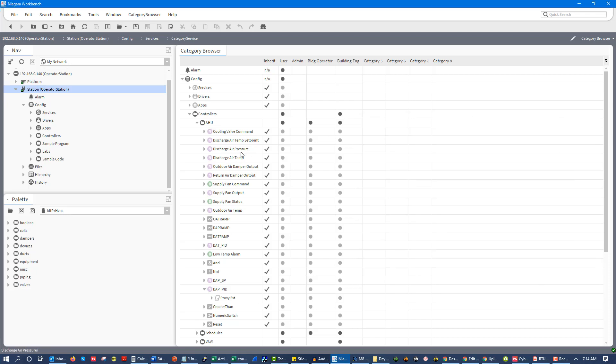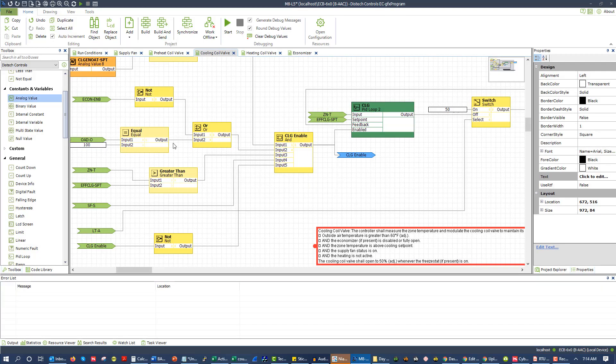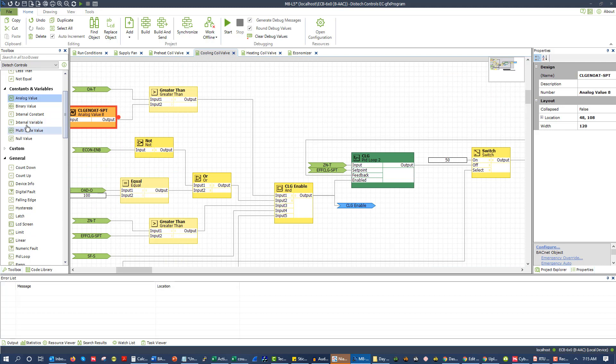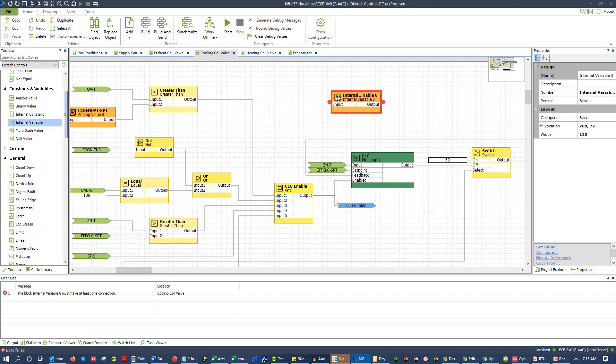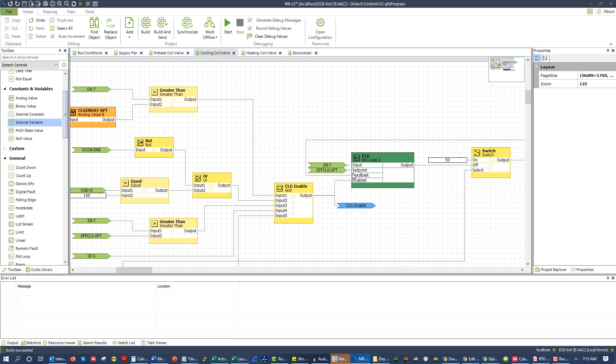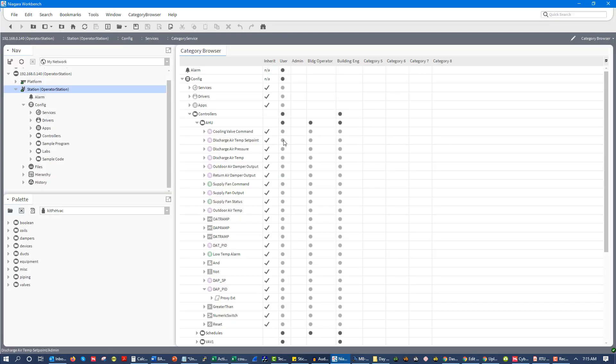Backups are especially important for a lot of us right now who, if you haven't already shut down your building and you're looking at going to shut down your building, you need to perform a backup. Because some of your points are not going to be persistent. If we open up this DISTECH software here and I add an internal variable and click on this, you'll see persists. That means when the controller resets, the value in here is going to persist. Well, there's some software where there is not persistent programming. The values are not persistent. So you really want to back them up because a lot of you are going to be turning off your buildings. You're going to go to turn back on your buildings and you're going to realize that all the settings have changed, and things are just going to be bad.